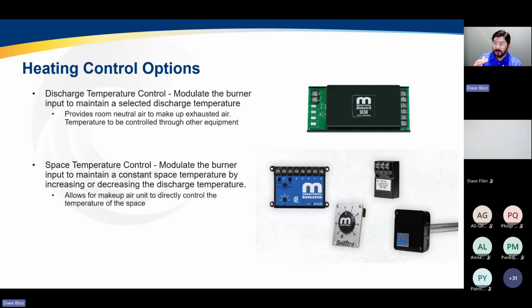Now, fully modulating heating controls could also mean two different types of modulating heat control options. So two types of control that we see often in these industrial retrofits is either I'm doing discharge temperature control or I'm doing space temperature control. Sometimes in these large makeup air applications, I just want my makeup air to deliver neutral, filtered, neutral air. So I'm constant discharge, but as my outdoor ambient changes and fluctuates, I need to actually still be able to modulate my gas flow, modulate my heat to maintain a constant discharge. And that's where our discharge temperature control solutions are typically delivered.